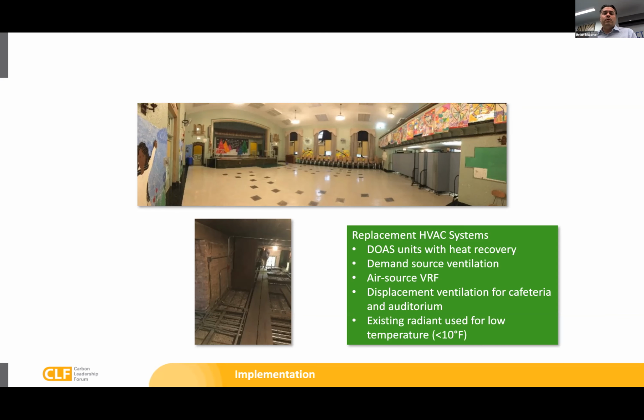However, due to the derate of the VRF systems at very low outdoor ambient temperatures, we needed to provide supplemental heating at certain times of the year. So the way the HVAC system is designed right now for the building, we're able to operate entirely on the air source VRF system down to about 10 degrees. Below 10 degrees, we transition over to the existing steam radiant system. So we're able to utilize existing infrastructure while providing this upgrade.